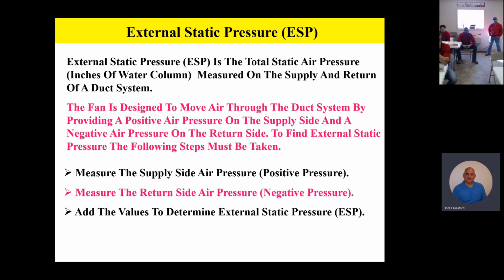Now, the way to think about external static is it's whatever is external to the fan. In other words, how much duct work, how many grills, how many components and how many elbows does the fan have to blow against on the positive side? All the components on the supply side of the duct system have resistance to the airflow, so the fan has to blow against that resistance. And on the return side, you're going to have filters and return grills and maybe some duct work.